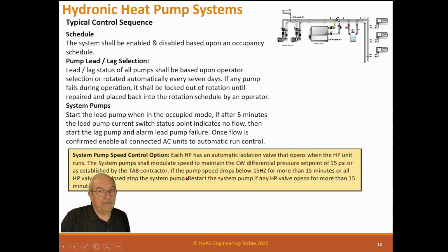Here's the pump speed one if you want to do that. Each heat pump has an automatic isolation valve that opens when the heat pump unit runs. The system pump shall modulate speed to maintain the condenser water differential pressure set point of 15 psi or whatever is established by the TAB contractor.